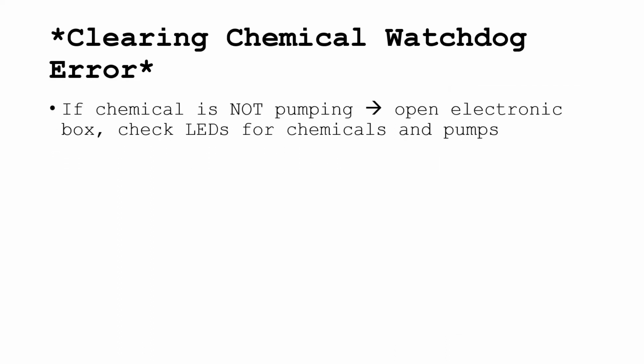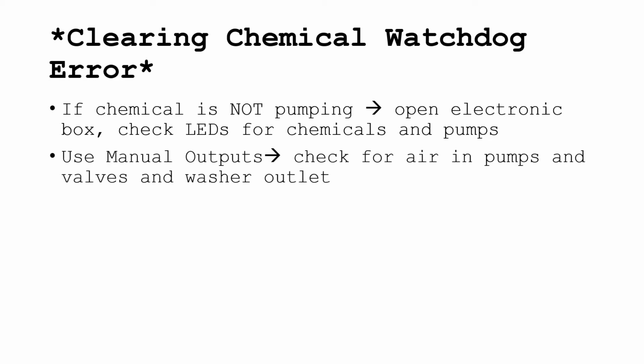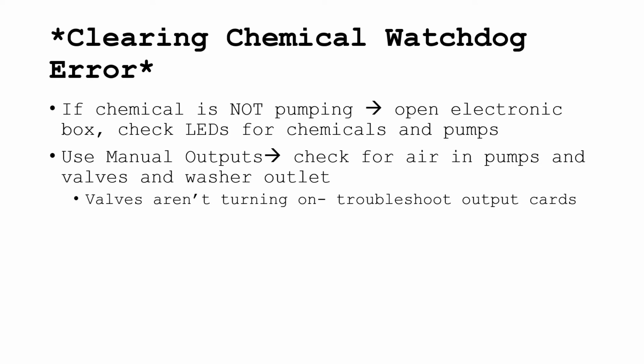If the chemical is not pumping, open the electronics box and check that the LED for the chemical and pump air pilot valves are lit up. Using the manual outputs screen, check for air at the pump and valves and the outlet line to the washer. If the valves are not turning on, troubleshoot the output cards in the controller. Check for voltage on the output.